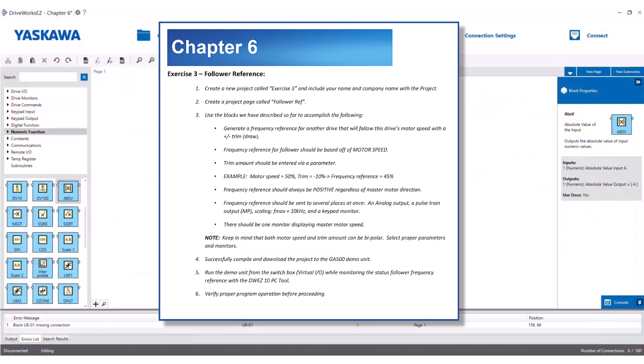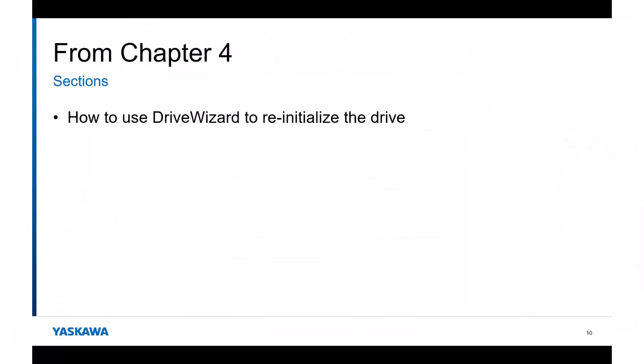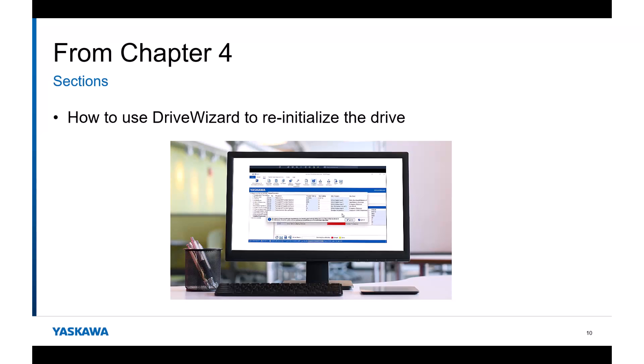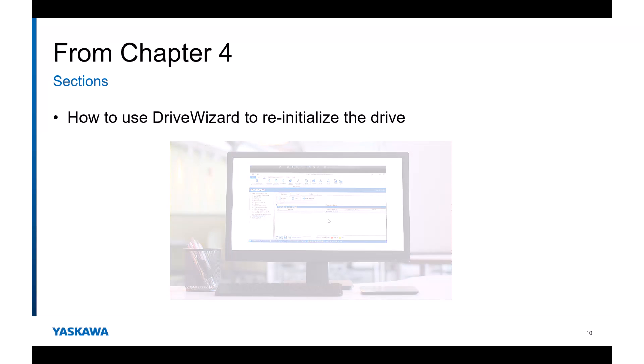After you have your project made, compile and download it to the GA500 demo unit. Run the demo unit from the Virtual I/O switch box while monitoring the status of the follower frequency reference with the DriveWorks Easy PC tool and verify proper program operation before proceeding. Pause this video and try to accomplish this on your own using Splashtop and the Virtual I/O application. Before you write your DriveWorks Easy project, do not forget to initialize the drive to clear out the previous DriveWorks Easy project, otherwise your program may not function properly since it still has leftover DriveWorks Easy functions set up in the drive's I/O from the previous exercise. You can refer back to Chapter 4 for an explanation of how to do this.